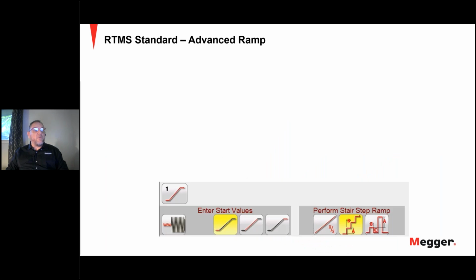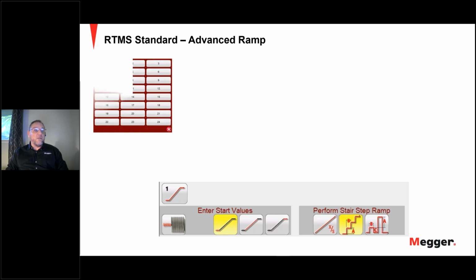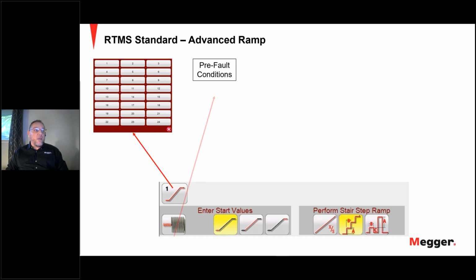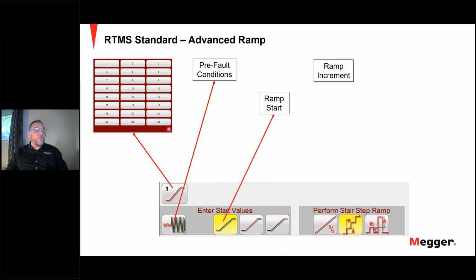Moving on to the advanced ramp. The advanced ramp has similarities to the simple ramp. Like in the simple ramp, up to 24 ramps may be selected, and the same with the advanced ramp. The primary differences between the simple and advanced ramp are the start, the increment and stop values, and the addition of the smooth ramp. So first of all, you've got the pre-fault condition, then you've got your ramp start condition, your ramp increment condition, and then your ramp end condition.